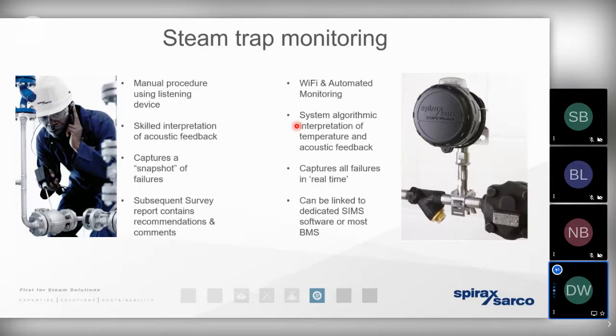But of course, if a steam trap fails in the open position, then not only are we losing that valuable energy in the steam to atmosphere, we're simply missing the opportunity to recover that condensate for the simple reason it's going to waste. So it's vitally important that those steam traps are monitored periodically.